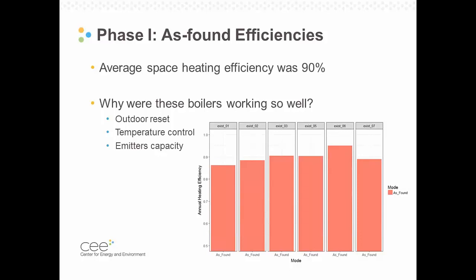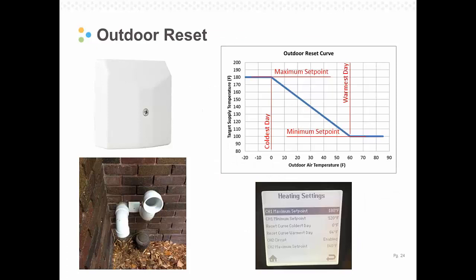But once we saw that these boilers were working really well, we dug into the data to figure out why they are working so well, and why some of the concerns that people have had about efficiency maybe are not seen in these systems. There were 3 main reasons for this, and they surrounded the outdoor reset, the temperature control of the boiler, and the emitters in the house. And so we'll walk through each of those factors.